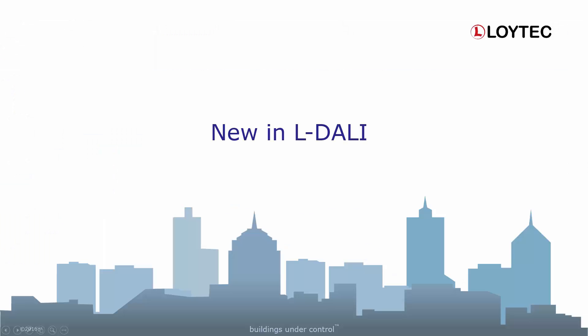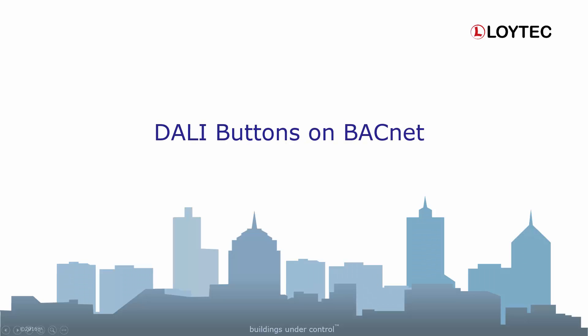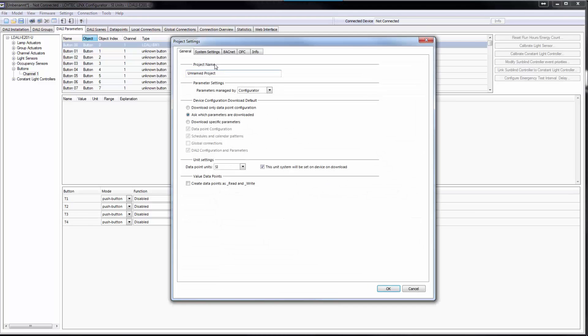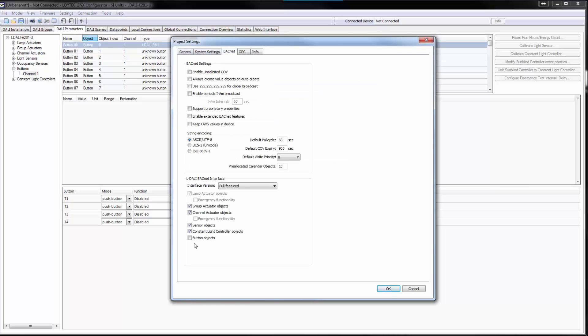In addition to the already shown features of the configurator, LDALI supports some extra features. For the BACnet LDALI models, the state of a button device input can now be forwarded to a BACnet binary input object as an alternative to directly control DALI lights. You just have to configure the BACnet interface to support the button objects.